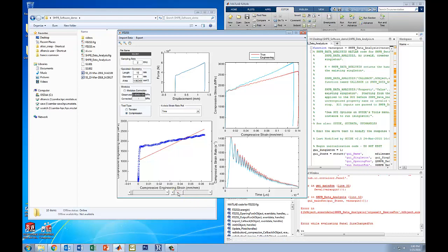What will commonly happen during tests is that this area will have little toes in the data. Just as an example here, you can see how it curves over, which physically doesn't make a lot of sense. So this tool enables you to clean up this area, since we won't use it for any modeling anyway, or any future work this could get passed on to.